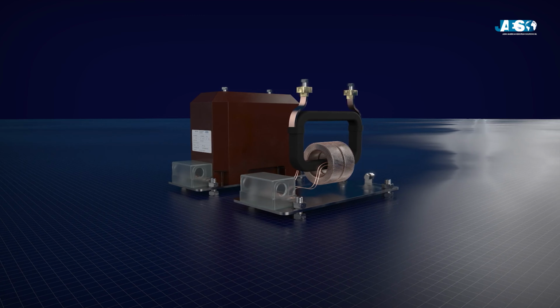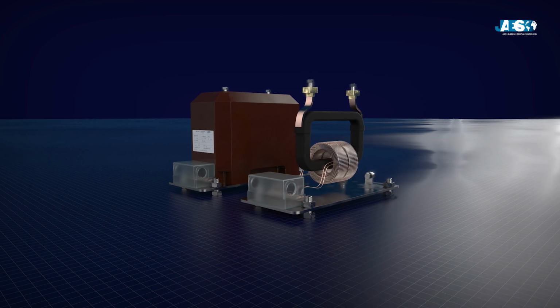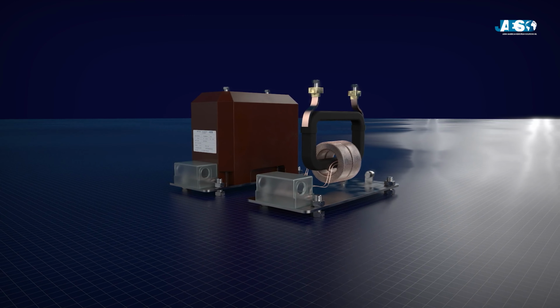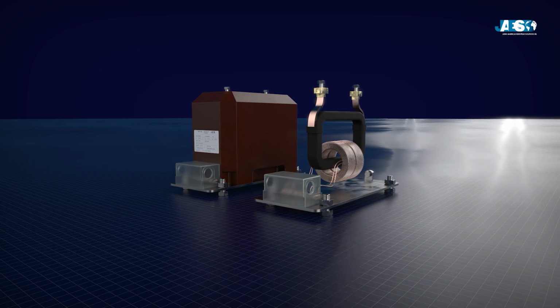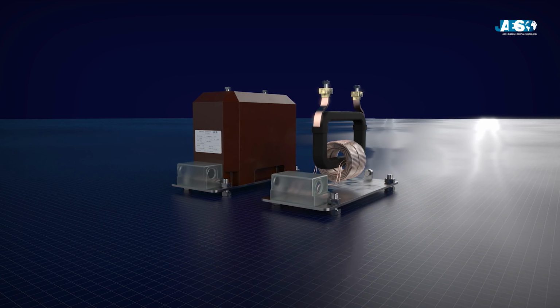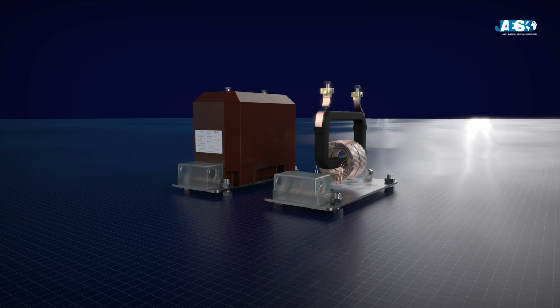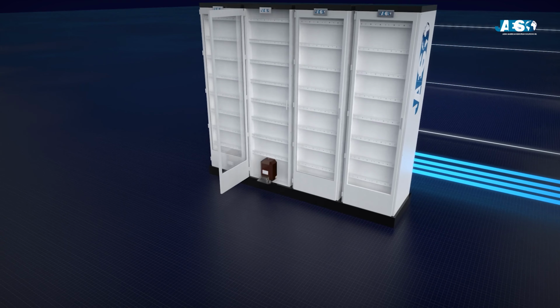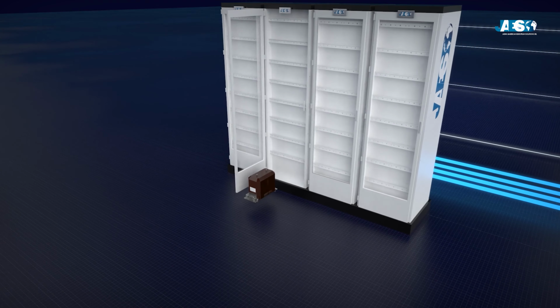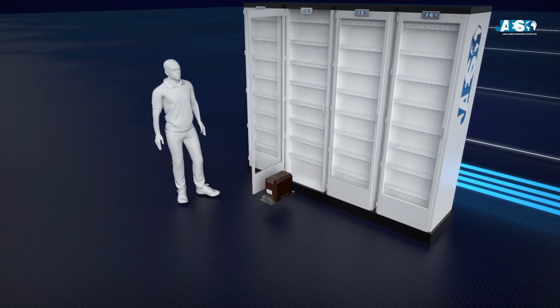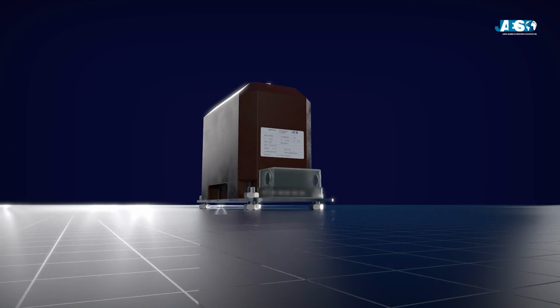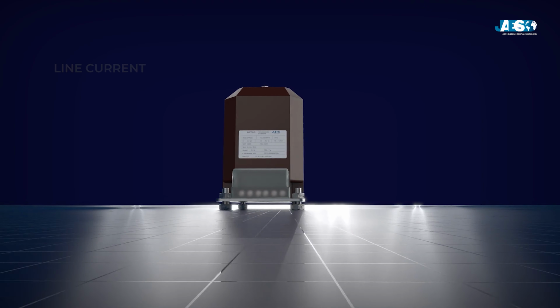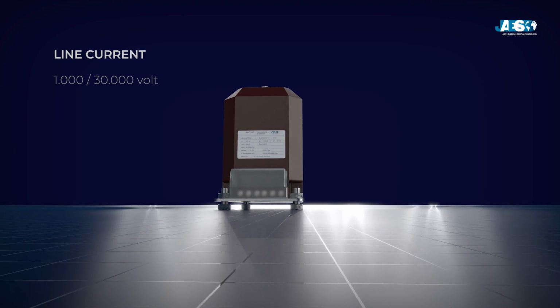A current reducer, or CT, is a transformer capable of supplying its output terminals with a current of a value congruent with the available measuring instruments and capable of faithfully representing the input current. Current reducers are mainly used in the measurement of high currents, which exceed the capacities of the measuring instruments, and in the measurement of currents on high voltage networks in order to isolate the reading circuit and the operator. Current transformers are typically used to reduce the line current to a standardized secondary value of 5 amps or 1 amp.